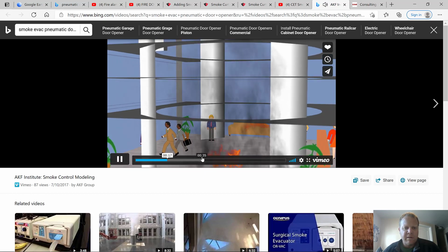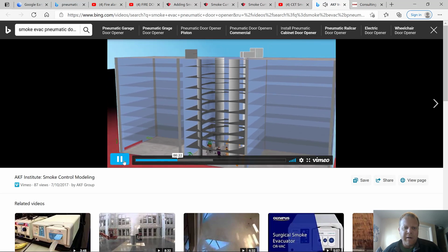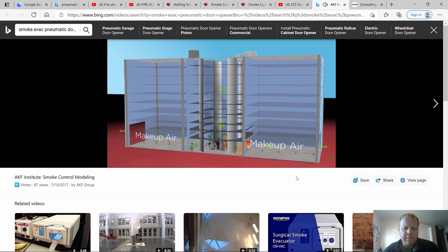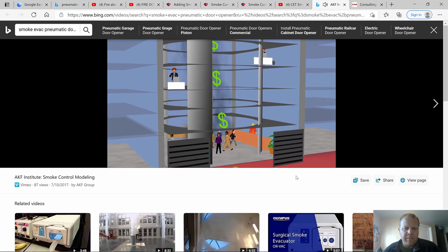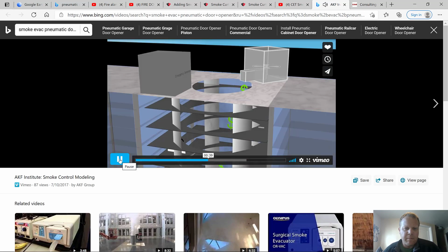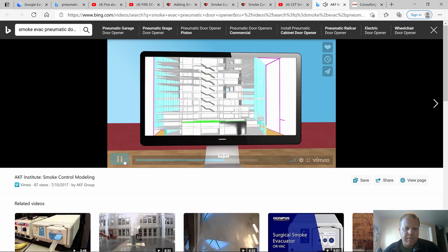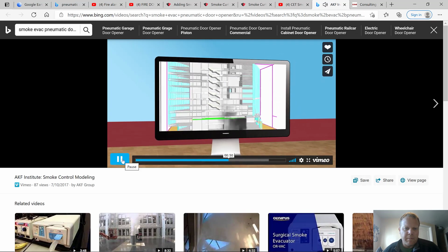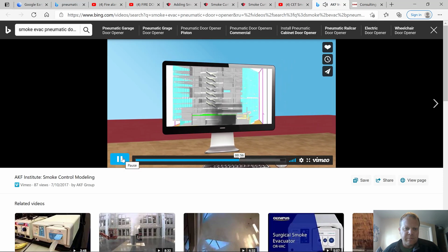Also an opportunity for the spread of smoke and fire throughout a building. So we've got an atrium. To ensure proper smoke evacuation, make-up air must be provided, typically by mechanical means, at the base of the shaft or atrium. Building codes require mechanical smoke control systems and provide a prescriptive formula for sizing these systems that is extremely conservative, typically resulting in oversized systems with considerable make-up air openings compromising the building's aesthetics. The code also allows for a performance-based design whereby computer modeling more accurately predicts the actual smoke movement in the building, resulting in a requirement for less airflow and smaller equipment.